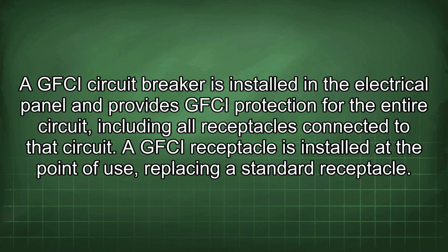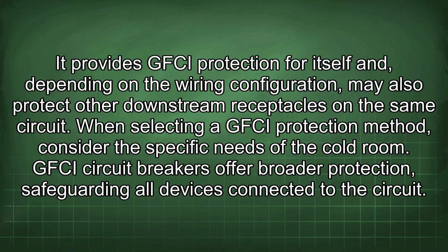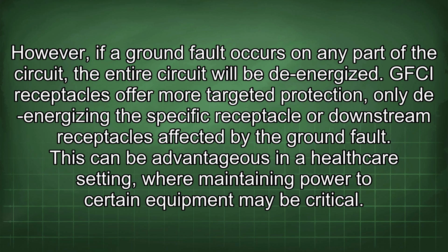A GFCI receptacle is installed at the point of use, replacing a standard receptacle. It provides GFCI protection for itself and, depending on the wiring configuration, may also protect other downstream receptacles on the same circuit. When selecting a GFCI protection method, consider the specific needs of the cold room. GFCI circuit breakers offer broader protection, safeguarding all devices connected to the circuit. However, if a ground fault occurs on any part of the circuit, the entire circuit will be de-energized. GFCI receptacles offer more targeted protection, only de-energizing the specific receptacle or downstream receptacles affected by the ground fault. This can be advantageous in a healthcare setting, where maintaining power to certain equipment may be critical.